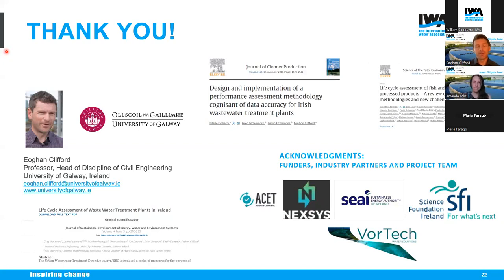If you're looking at a diffuser-based system, what you have said is very true. You would need to look at diffuser fouling and try to estimate how that impacts oxygen transfer efficiency, because that and the electricity grid efficiency are by far the two key inputs to this model. That's what we've seen, and that would be the same for all aeration systems. For diffuser-based systems, you would probably also have to include maintenance, simply because the maintenance of those systems tends to be a little more complex when they do foul completely.